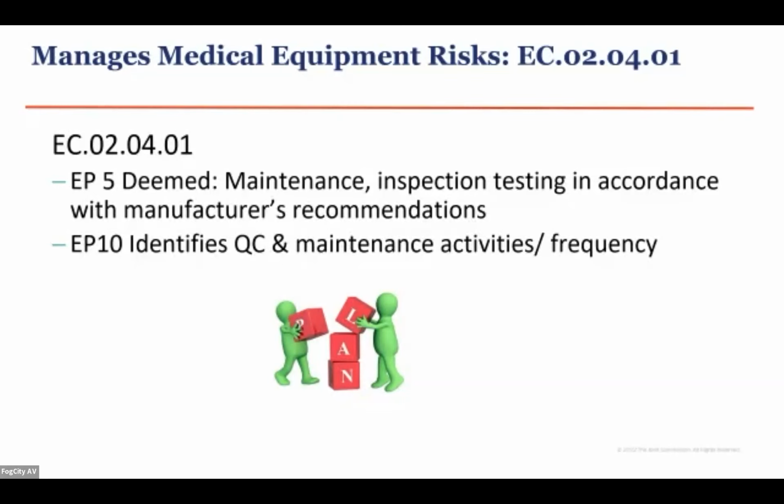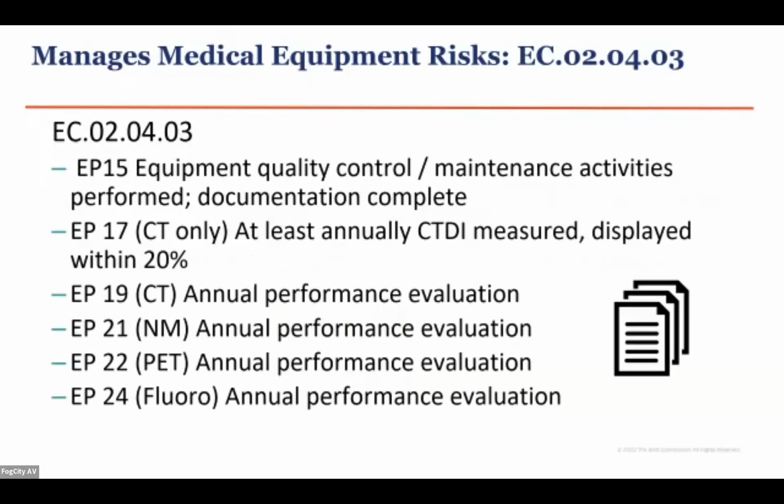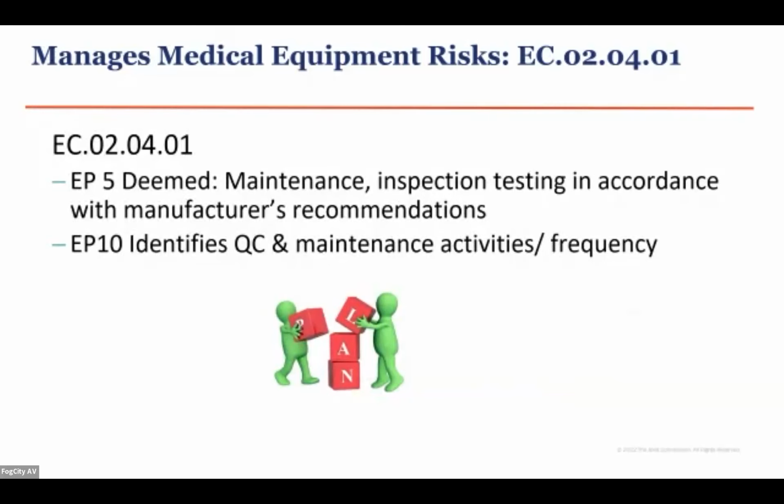It says if you're one of those organizations that we're doing a survey for CMS, you need to have maintenance and inspection testing of your medical equipment, which includes imaging. Imaging equipment is classed as medical equipment that follows manufacturer's recommendations. So one of the things that a surveyor often asks is, do you know what the manufacturer recommends? And how do you know that? Do you have the manufacturer's recommendation someplace? So that's something you might consider when you're involved in a survey.